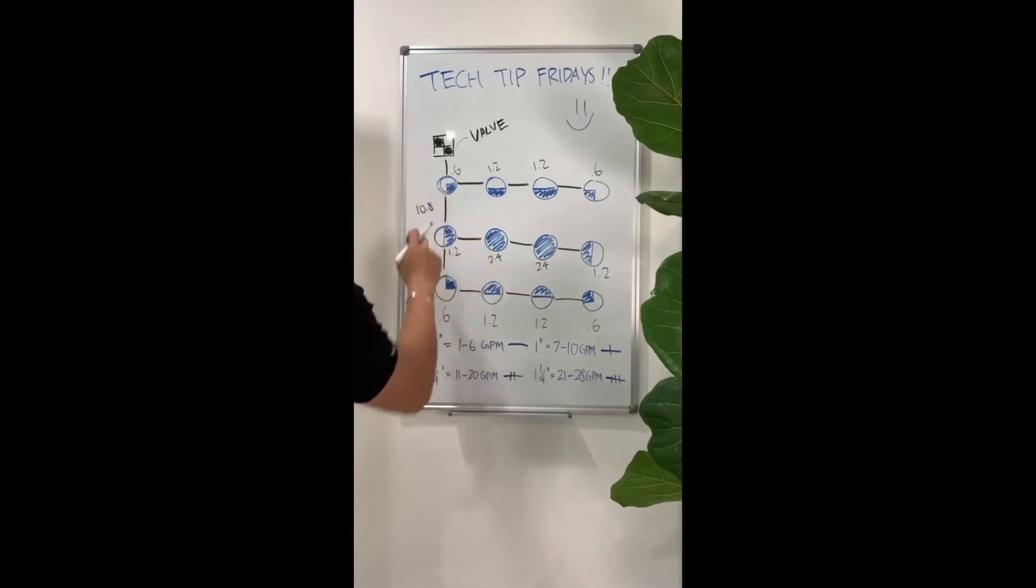Now if it's 10.8 GPMs, you see that 1 inch can do 7 to 10 and 1 and a quarter can do 11 to 20. So I always like to round up just to give ourselves some more wiggle room. So this section of pipe would be 1 and a quarter inch, which is two tick marks. So I'll go ahead and put two tick marks right there.